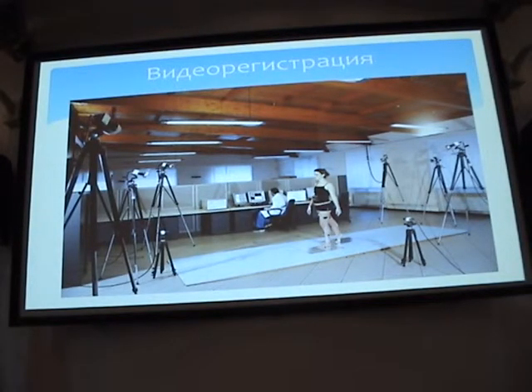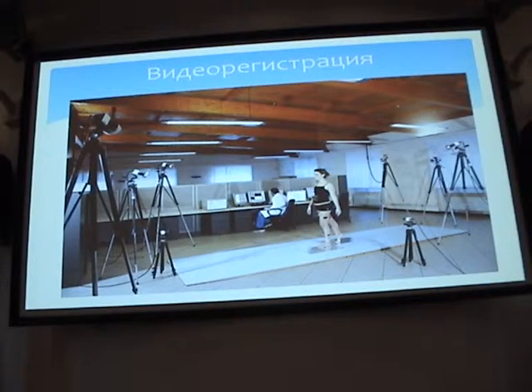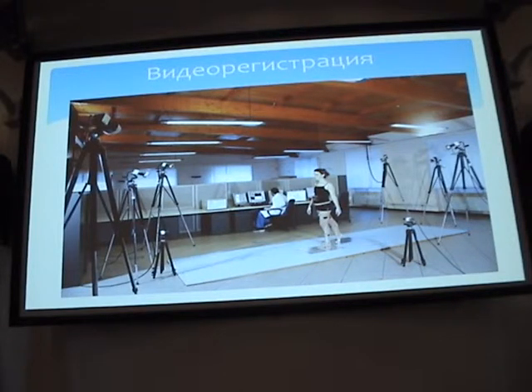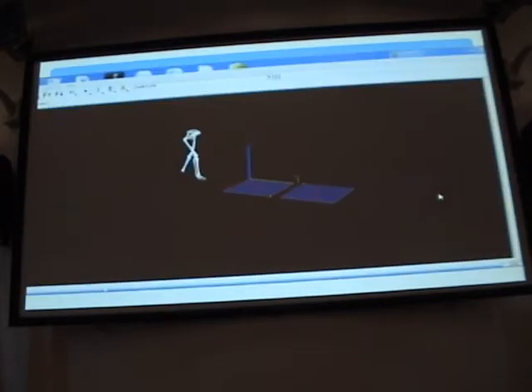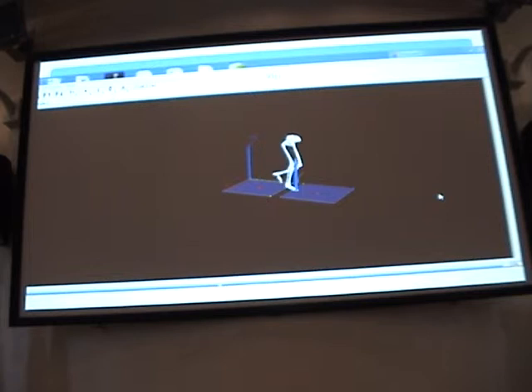For studying kinematics, we do video registration. On this slide you see a typical motion analysis laboratory — a quite large room with many cameras installed at different angles along the perimeter. There are light-reflectant markers — sometimes luminous LED markers — placed on the patient's body. For registration of each marker in space, two or three cameras must be able to register simultaneously. Sometimes patients turn around, and we need many more markers and cameras. This is the result of video registration as presented on the monitor.